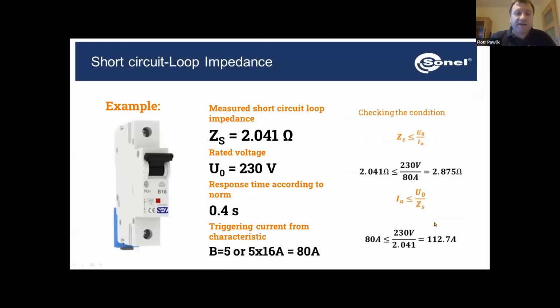So let's look at the example. We have our network. Let's say this is a TN system, so with 230 volts AC. So the disconnection time is 0.4 seconds. That's the required time for the automatic disconnection of supply. We are having here the MCB type B16. So for B, this will be 5 times 16, so the 80 amps, that's the current which will cause our breaker to disconnect within 0.4 seconds.